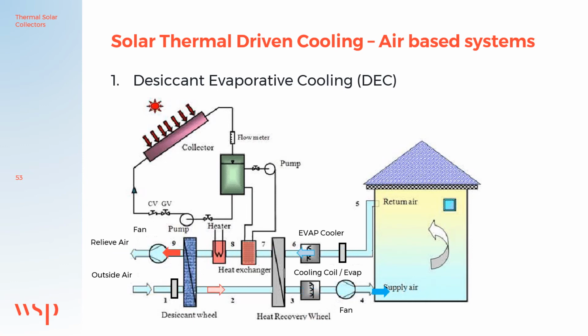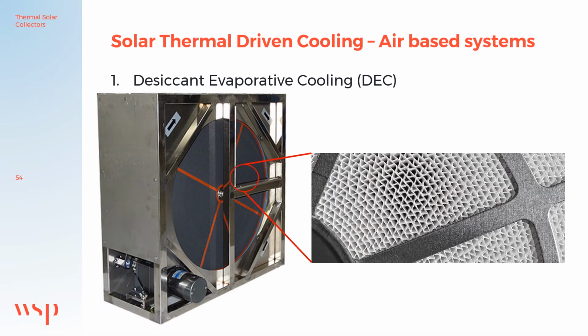The free heat from the solar collector indirectly removes the humidity from the outside air and utilizes cooling from evaporative coolers to cool down the space or heat up the space. The system uses very little electrical energy. A heat recovery wheel as well as a desiccant wheel with silica gel is used in this process as well. This is an example of a desiccant wheel on the left and a close-up of the holes, or flutes as they call it, in the wheel surface on the right. These wheels rotate slowly at approximately 12 to 16 revolutions per minute and can transfer sensible or latent heat or both.